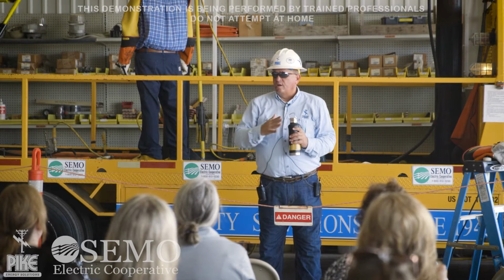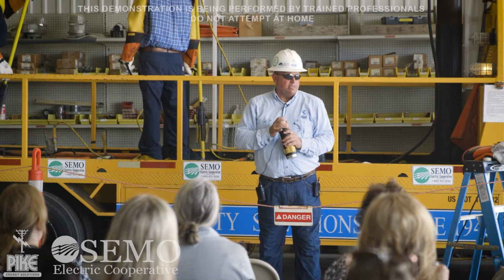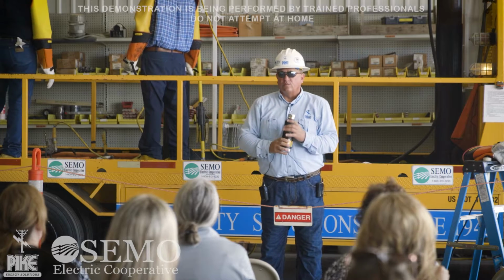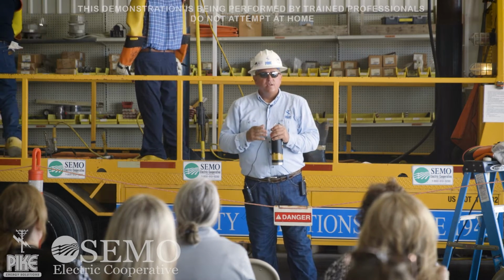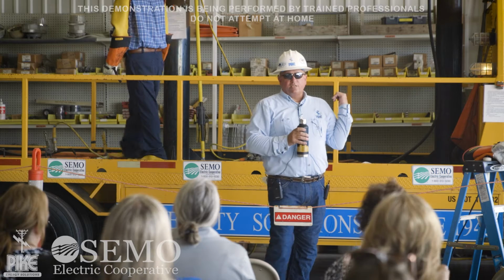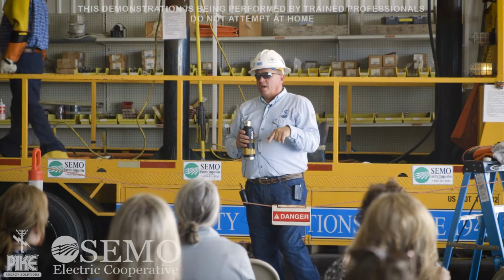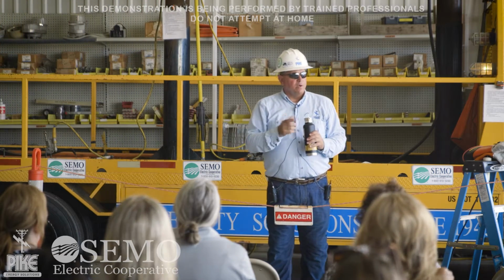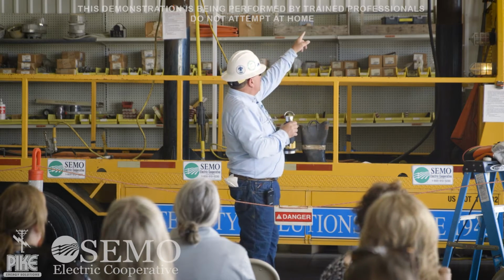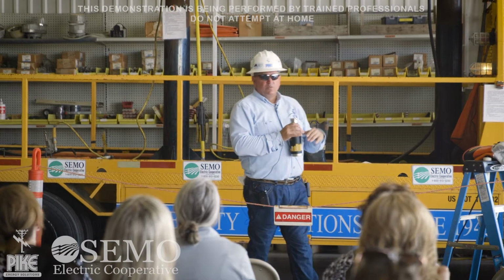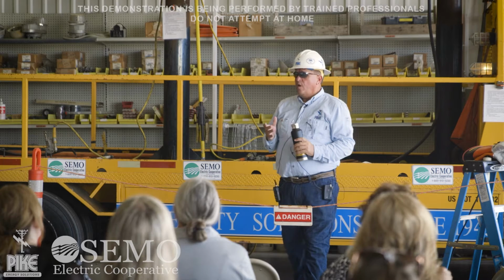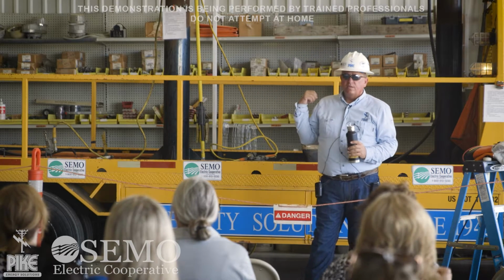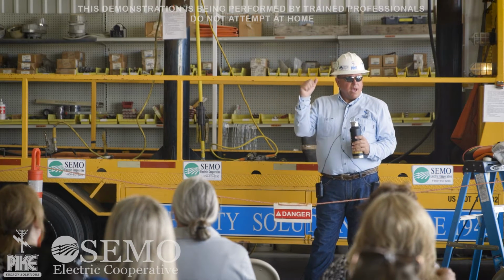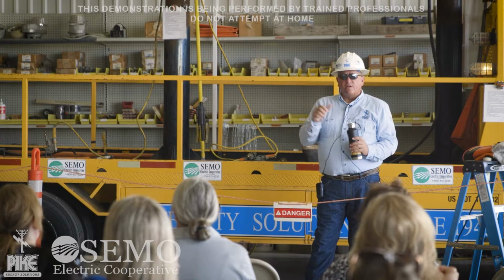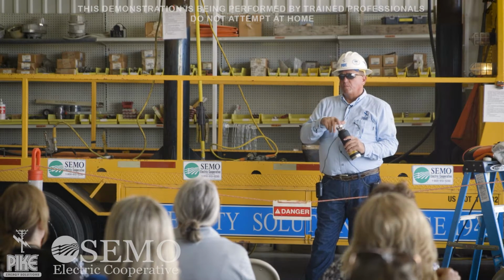It leaves there and goes to substations, hits the substations, and is stepped down to distribution voltage. It leaves there and goes to our homes and hits these transformers, stepping it down again. But that transformer - exactly what we did right here - we've taken that lead and moved it over to the top. So now we're using that same voltage to backfeed that transformer, and we should be able to get around 7,000 volts or a little bit more.